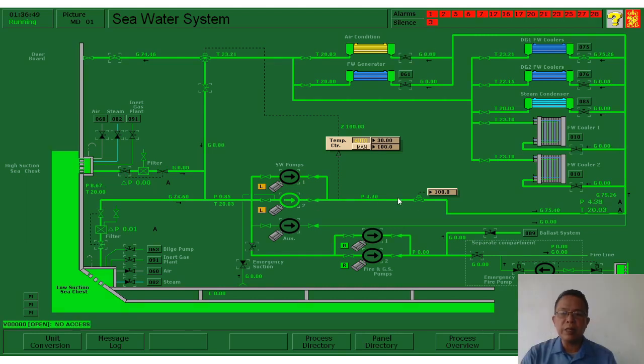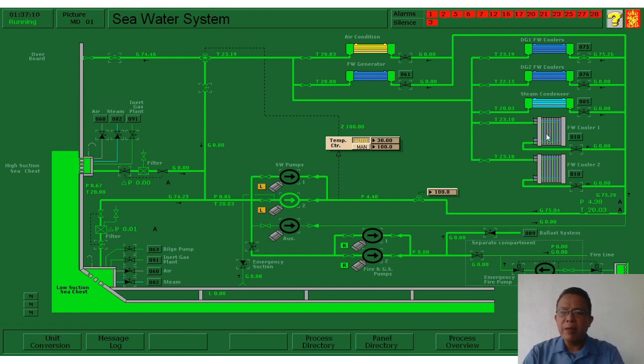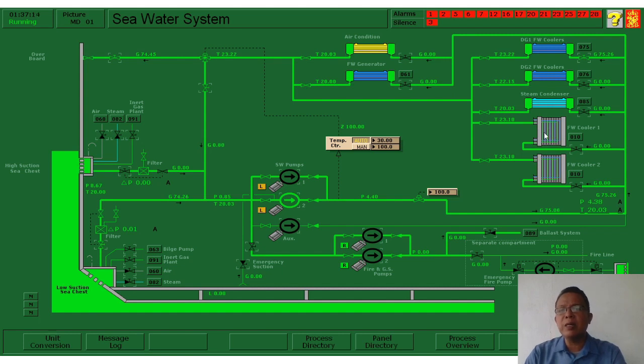The connection output goes all the way to the cooler. We have here freshwater cooler number one and freshwater cooler number two. These two coolers are our main engine jacket water coolers. There are two units because when one is being used, the other one is on standby. If one is dirty, we can clean it while the other is on standby.